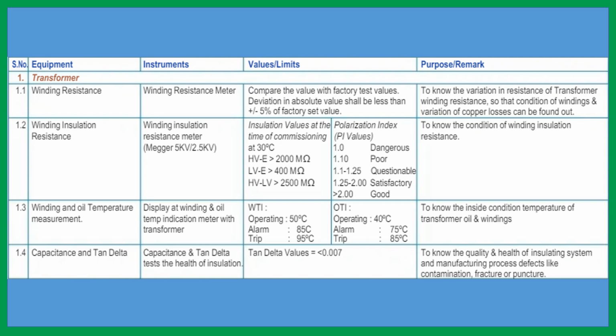Next is tan delta. What is tan delta? We know our bushings are condenser bushings, so we measure the tan delta. In a pure capacitor, current leads voltage by 90 degrees, but nothing is pure. Some loss will be there. It is theoretically pure, but due to this loss, an angle is formed. The current will deviate by a delta angle from its 90 degree position, and it is called delta, and its tan is called tan delta. And what is its satisfactory value? Tan delta values should be less than or equal to 0.007. This is tan delta.